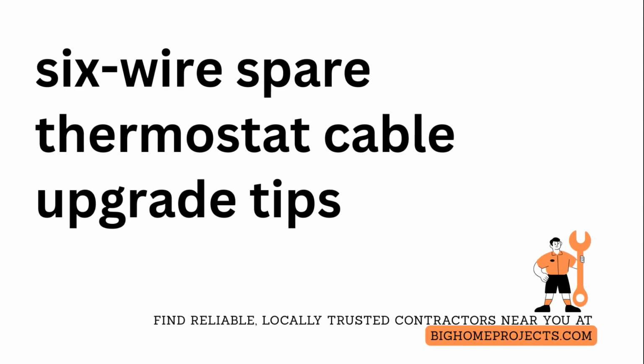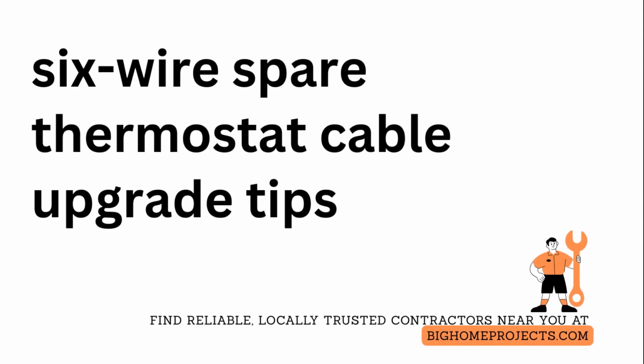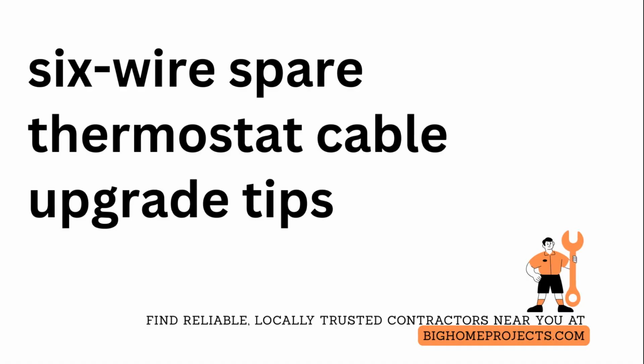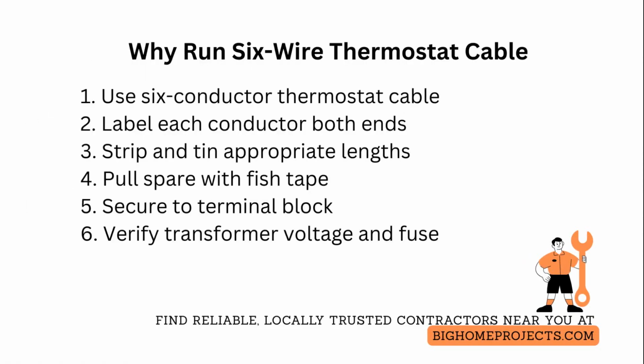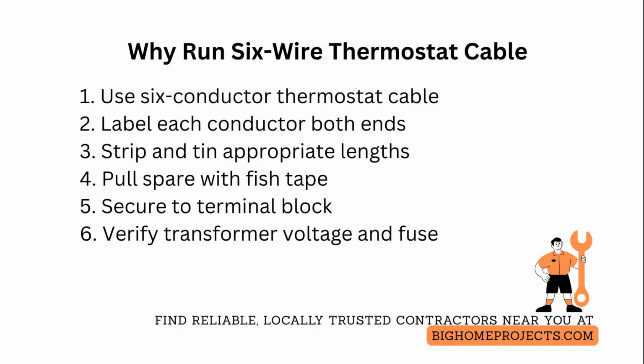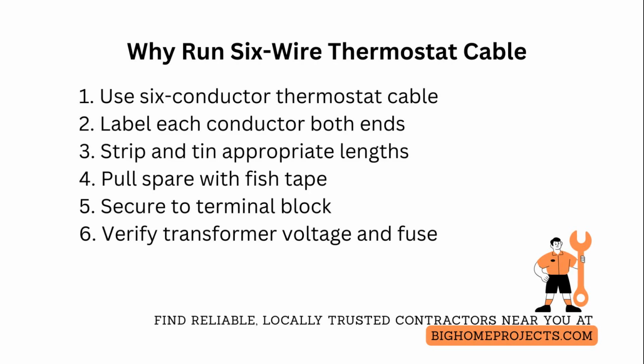If your thermostat job says you need 5 wires, run a 6-wire cable now so you won't have to rewire later. If you are replacing thermostat wiring and the installer or guide calls for 5 wires, choose a 6-conductor thermostat cable and label each conductor at both ends before you touch the terminals. This prevents confusion when routing through the attic, crawl space, or wall cavity.